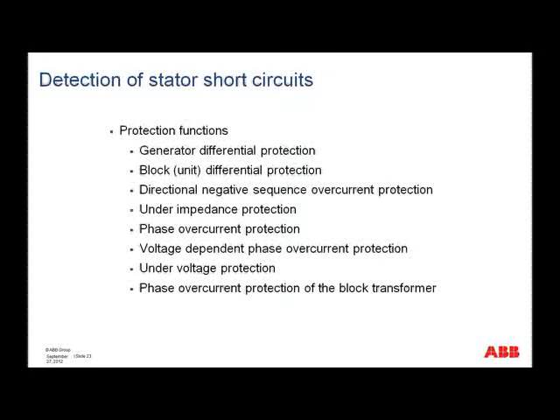So if we look then at what protection functions we have that can detect these stator short circuits, you will see, of course, there's the generator differential protection, there's the block or unit differential protection, okay, and if this is the 87U function, then as well as covering the generator, it will also include the unit transformer, but it may be a little bit less sensitive. The pickup sensitivity may be a little bit less than what we can set for the 87G.